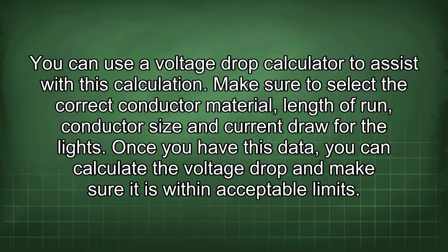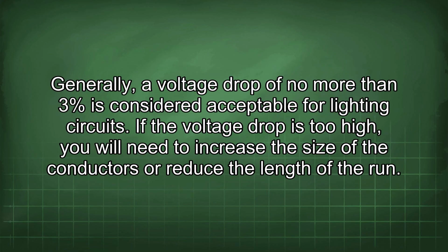Make sure to select the correct conductor material, length of run, conductor size, and current draw for the lights. Once you have this data, you can calculate the voltage drop and make sure it is within acceptable limits. Generally, a voltage drop of no more than 3% is considered acceptable for lighting circuits. If the voltage drop is too high, you will need to increase the size of the conductors or reduce the length of the run.